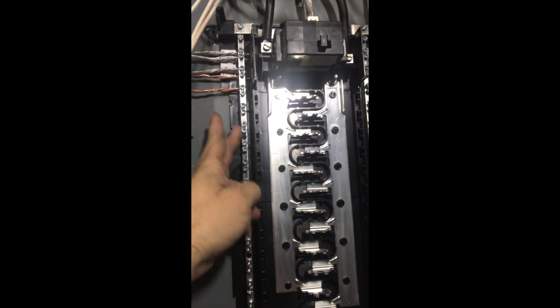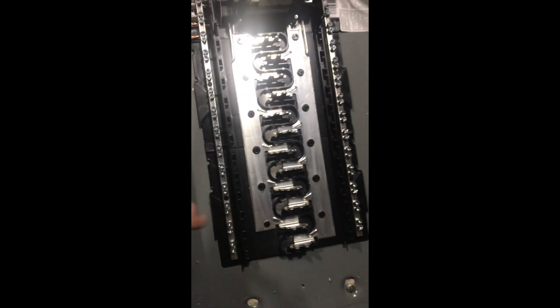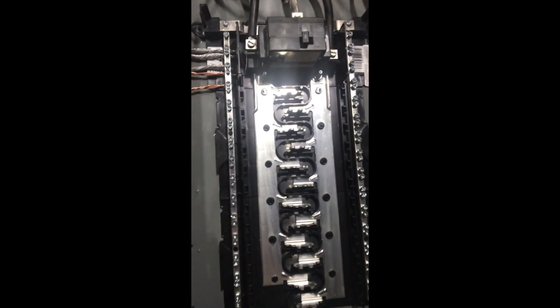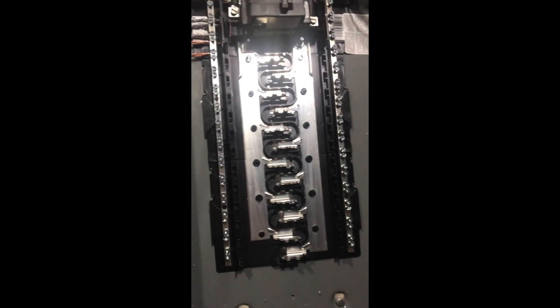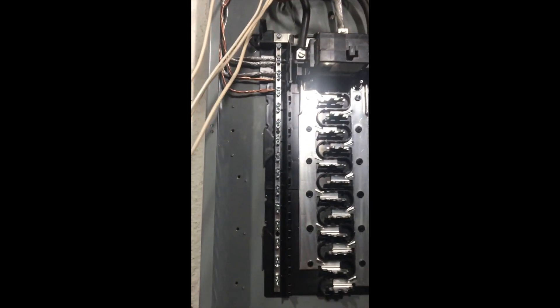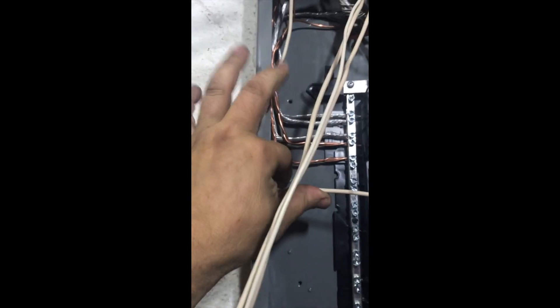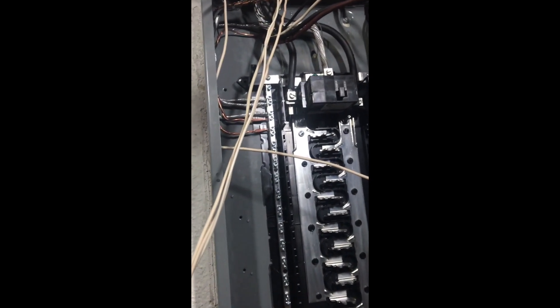Grounds can be doubled up — I try to put two, not more than three usually. These terminals are rated based on circular mils, which is the unit of measurement for wire. As long as the doubled-up wires don't exceed the circular mils of that terminal, you can put them underneath there. Grounds are non-current-carrying conductors — they're the alternate path, like a drain, so the fault current goes to ground instead of through you. Next step is to put the neutrals in — train them back nice and easy, only takes a few seconds.